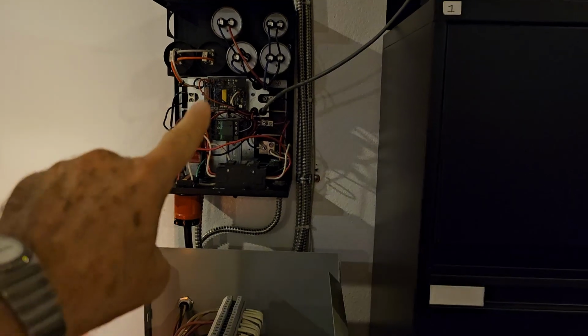What that makes me is suspicious of the 3-phase panel. Why can't the rest of the 3-phase panel have the same voltage, come out with 241.5? Why is it so high? Now, I talked to them and they said, well, when you've got a load on it, you turn the machine on, and then it should balance out this 3-phase panel, and it should all read in the 240 range there, which means that once it goes through the transformer, then it should be 230 range. But I don't know. This is awfully high. He was talking a couple of volts, 5 volts, maybe 7, 8 volts, maybe 10. But I'm talking 15, 20, 25 volts over. So that makes me suspicious that this guy is no good. There's something wrong with the 3-phase panel, and that guy needs to be replaced.